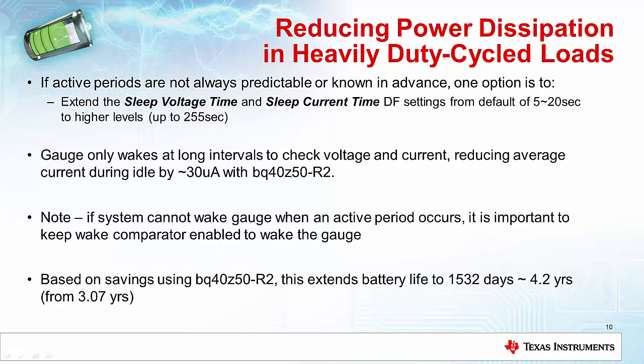Now another approach is if you have a system where the activity periods are not really predictable or can't be scheduled, you can actually leave the gauge running, but you can instead go in and modify some of the parameters that control how often it wakes up to measure voltage and current while in sleep mode. These are set in DF settings. Defaults are typically on the order of 5, 10, 20 seconds or so, but these can be programmed up to 255 seconds. And so then you can save considerable power if you take it from defaults.